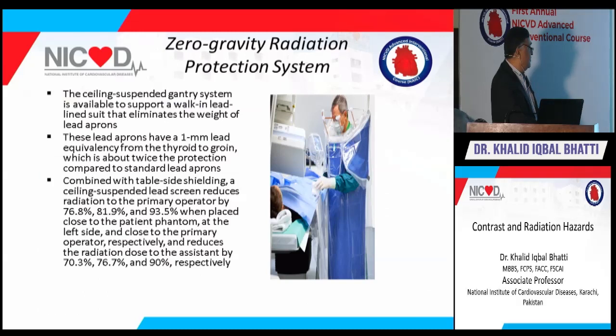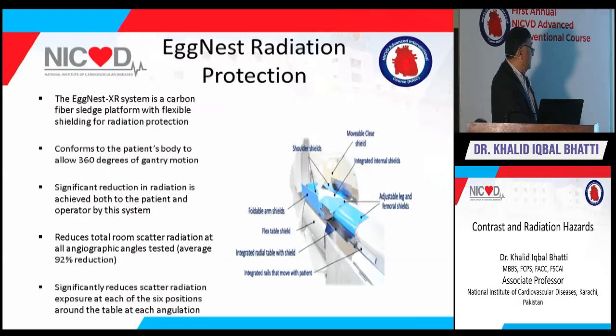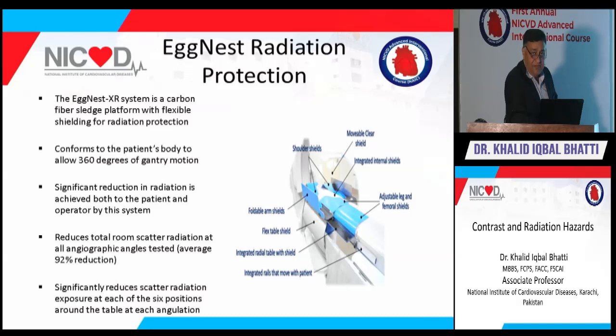Advanced protection systems include the zero-gravity radiation protection system and ceiling-suspended gantry systems that support the weight of lead suits, which provide 1 mm lead equivalency from thyroid to groin. The EggNest radiation protection system is a carbon fibre platform with flexible shielding that contours to the patient's body and allows 360-degree gantry motion.